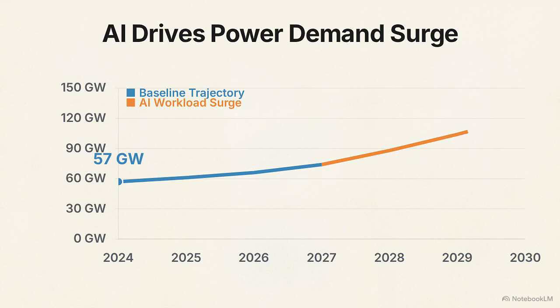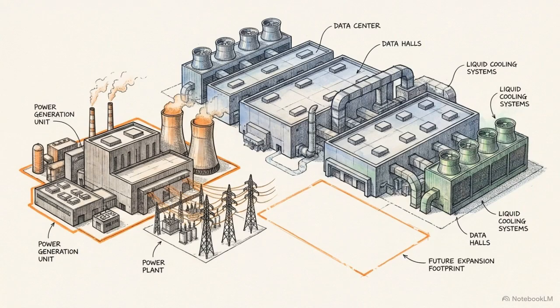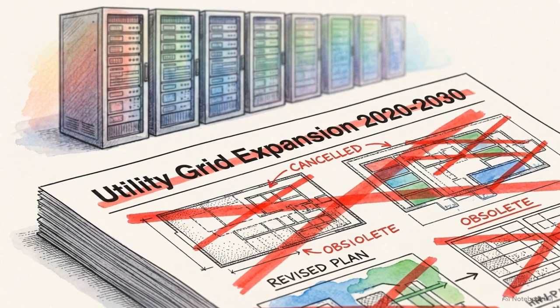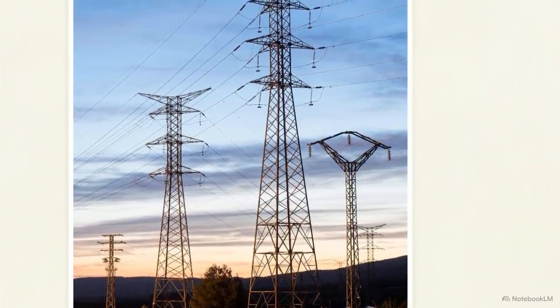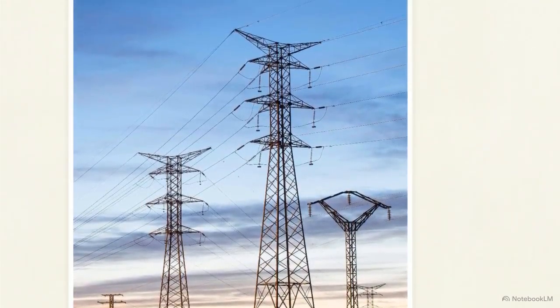We are currently at a baseline of 57 gigawatts. By 2030, that demand is projected to reach 122 gigawatts. Meeting this demand requires the industry to double the global power plant capacity dedicated specifically to data centers by the end of the decade. Current AI infrastructure requirements outpace legacy utility planning, making historical grid capacity forecasts and development timelines obsolete. The physical bottleneck lies in the transmission network.